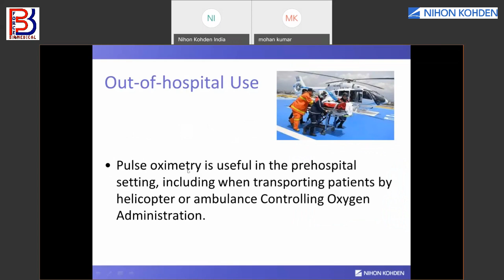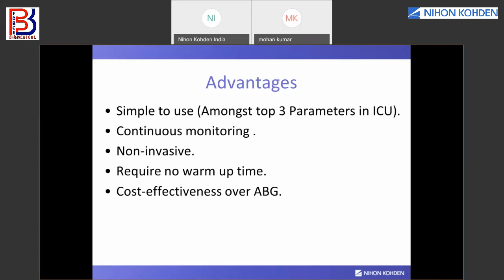So, advantages of SpO2. SpO2 is considered one of the top 3 parameters, which is very simple to use, it is continuous monitoring, and it is also a non-invasive method. And it doesn't require any warm-up time. As you connect an SpO2 probe, within 2-3 seconds it starts picking up the signals and gives the patient condition. And since in SpO2 we don't use any kind of accessories or reagents, it is very cost effective compared to ABG, which is arterial blood gas analyzers.